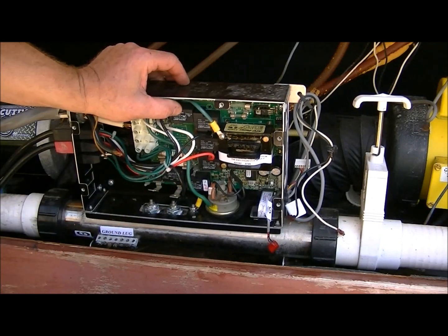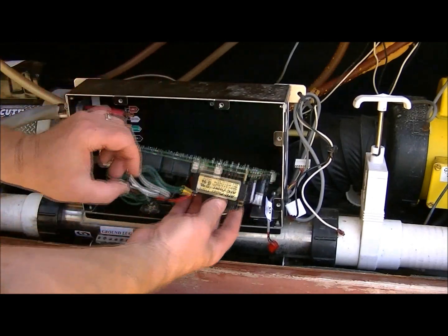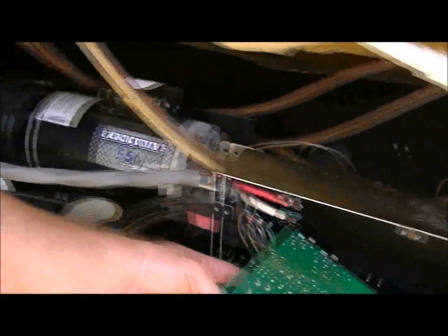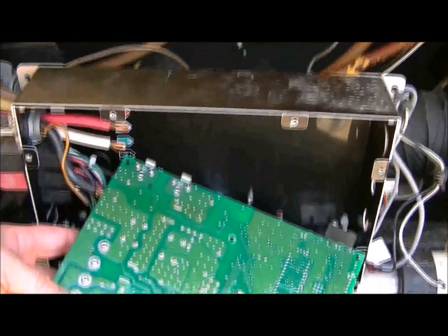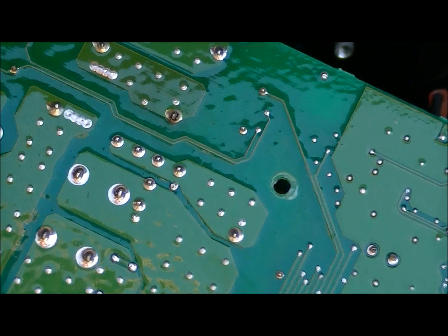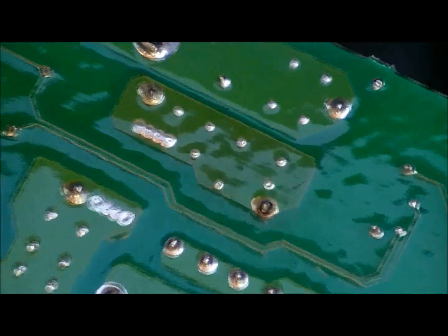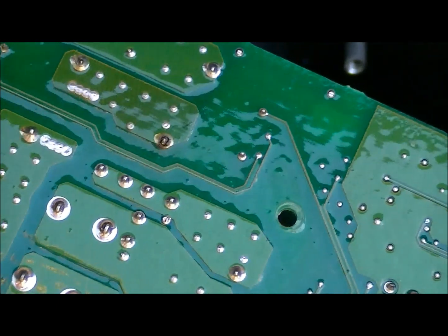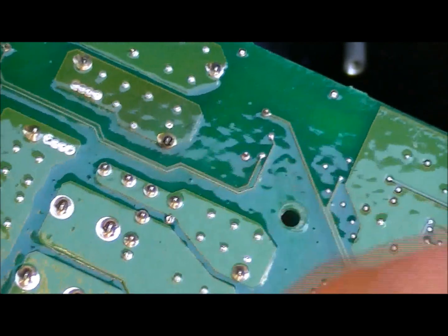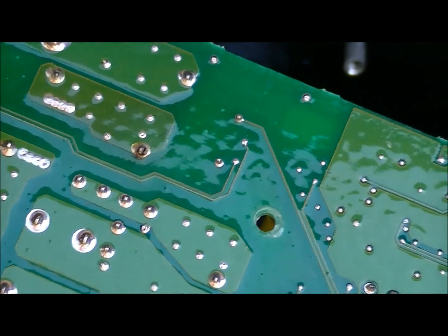This relay here — I've already set it. I'll zoom in and see how well we can see it. You can just see that spot right there, and it's a little dark around there. That's because that solder has melted away.